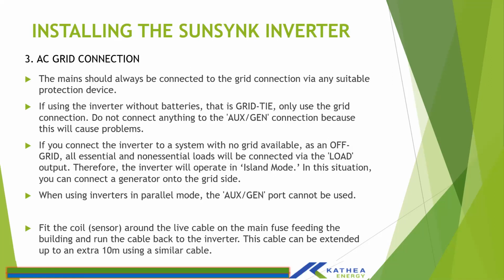However, if you are using the inverter as off-grid, that is in remote areas where there is no grid at all, loads should be connected on the load port, right? Because when the inverter is operating in island mode, it can only supply loads connected on the load port. That is, when you lose grid or in off-grid scenarios, the only port that will have output will be the load port. So both essential and non-essential loads will need to be connected through this port. And when you're connecting in this scenario, you can now connect your generator on the grid point, right? And the generator will basically act as a grid to the inverter. So when you're in off-grid mode, you can use the grid point to connect your generator, right?